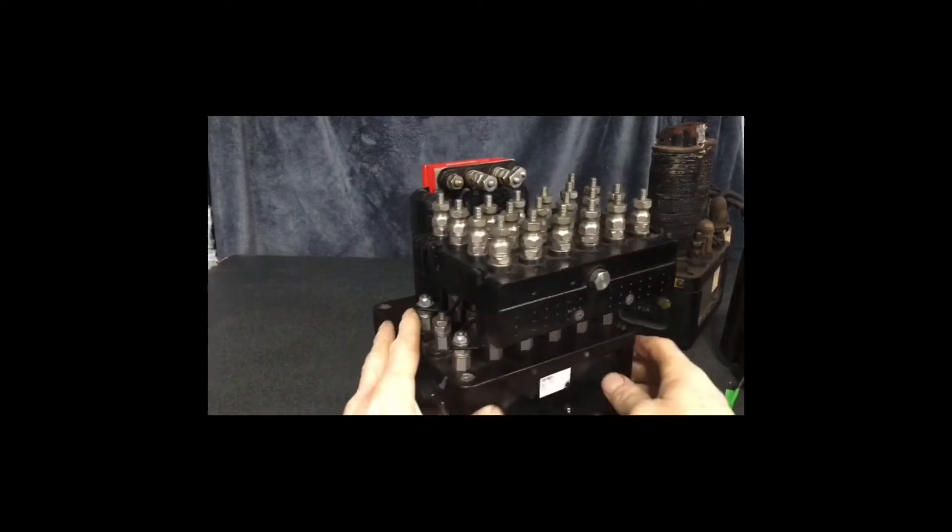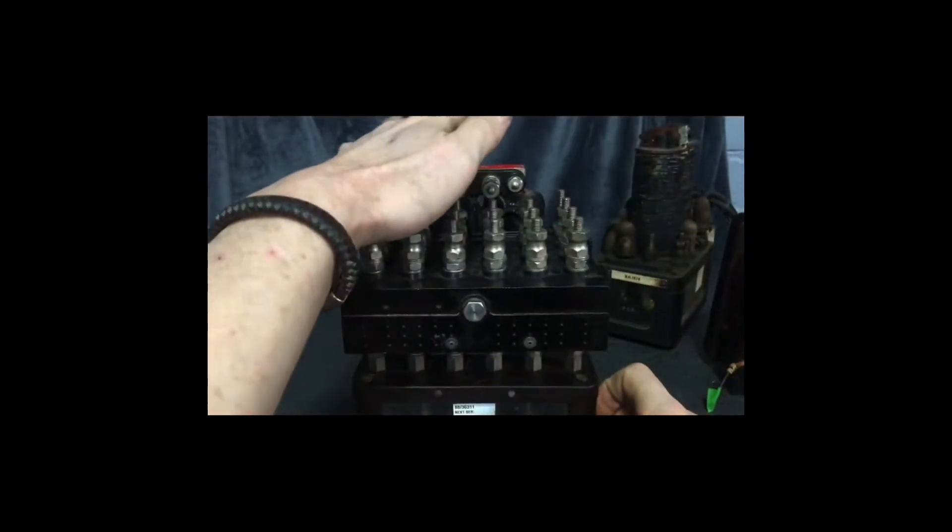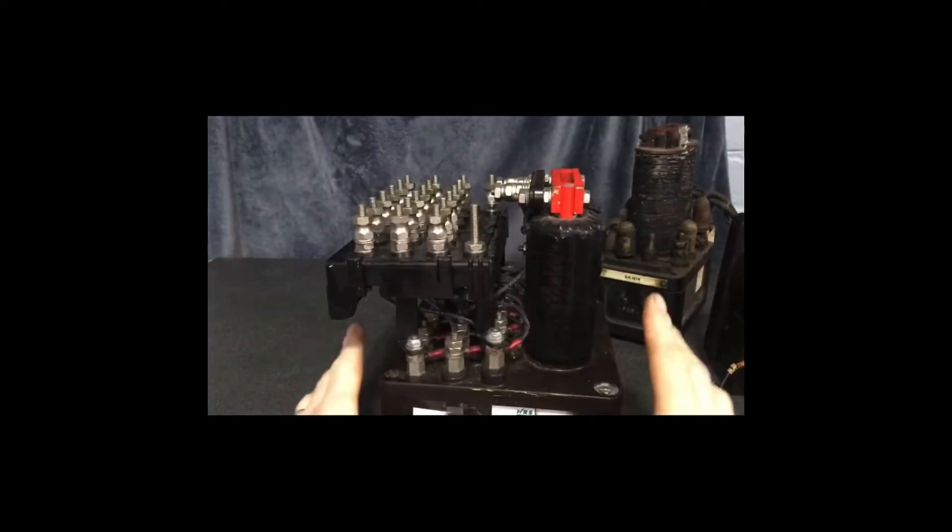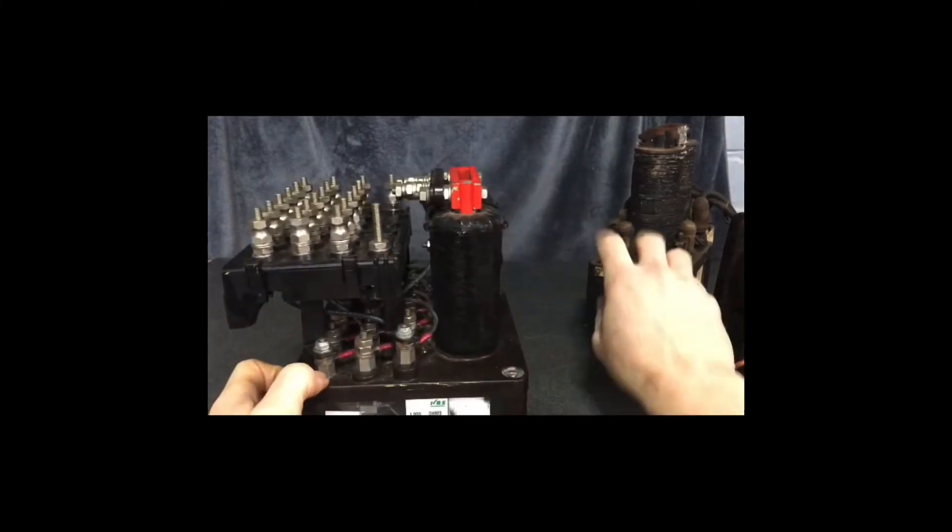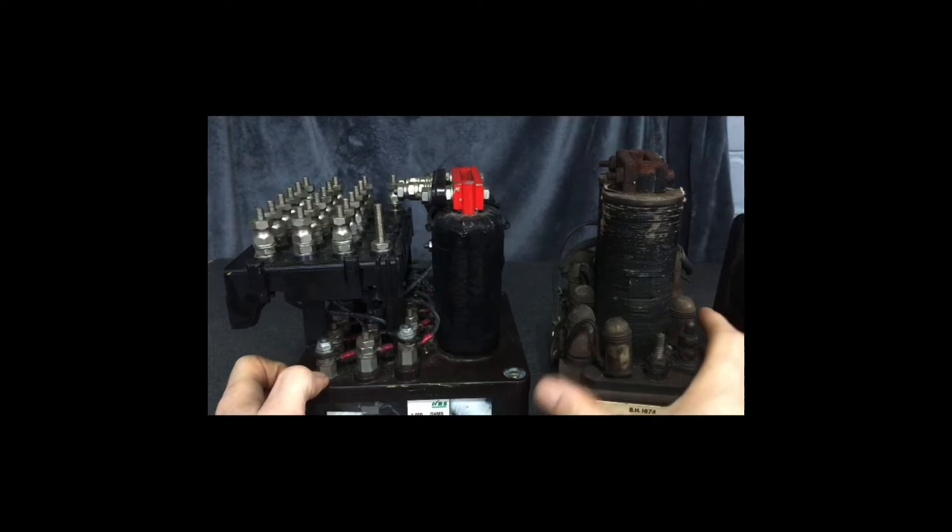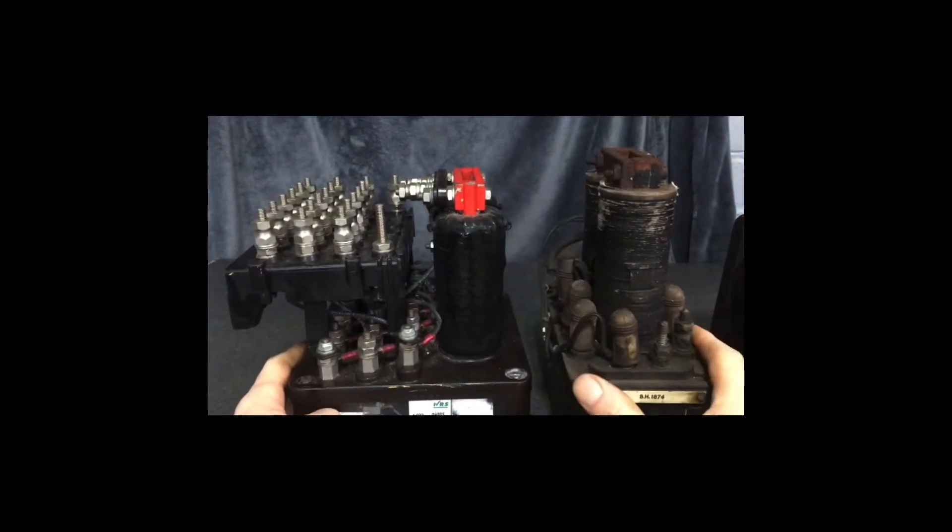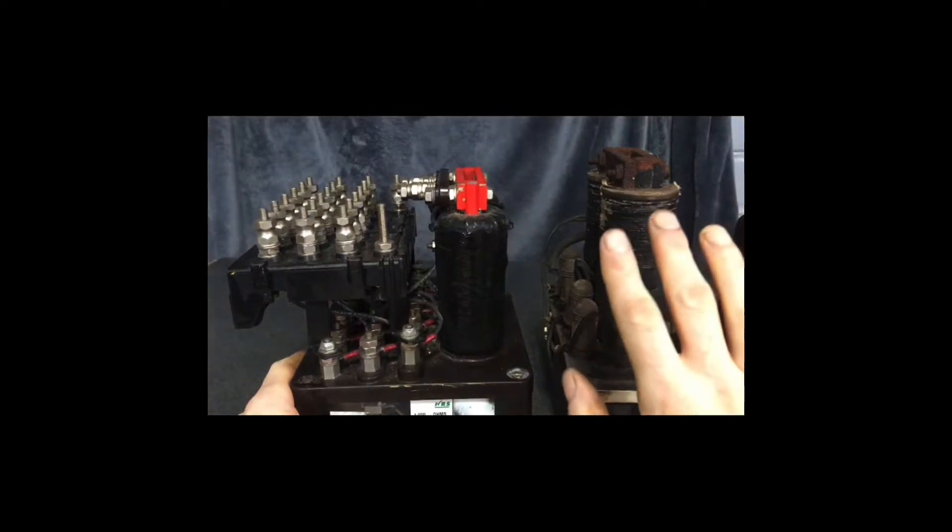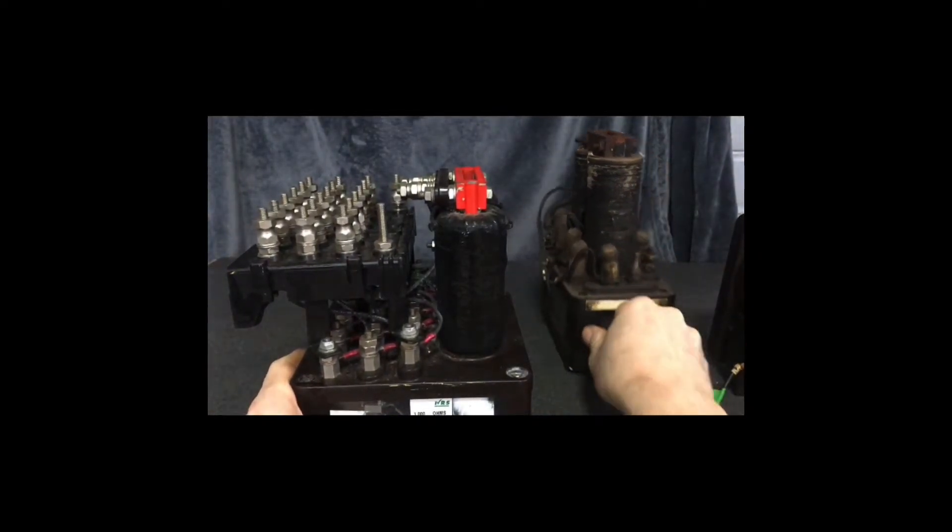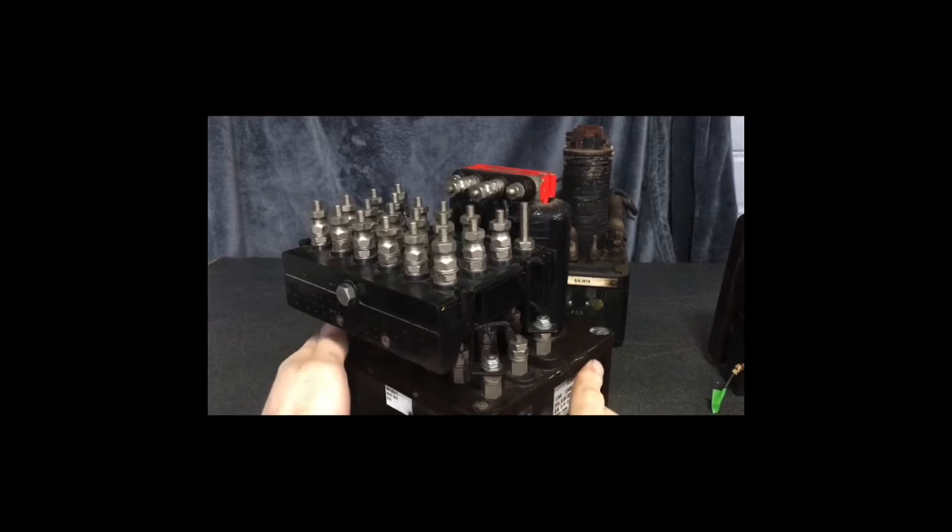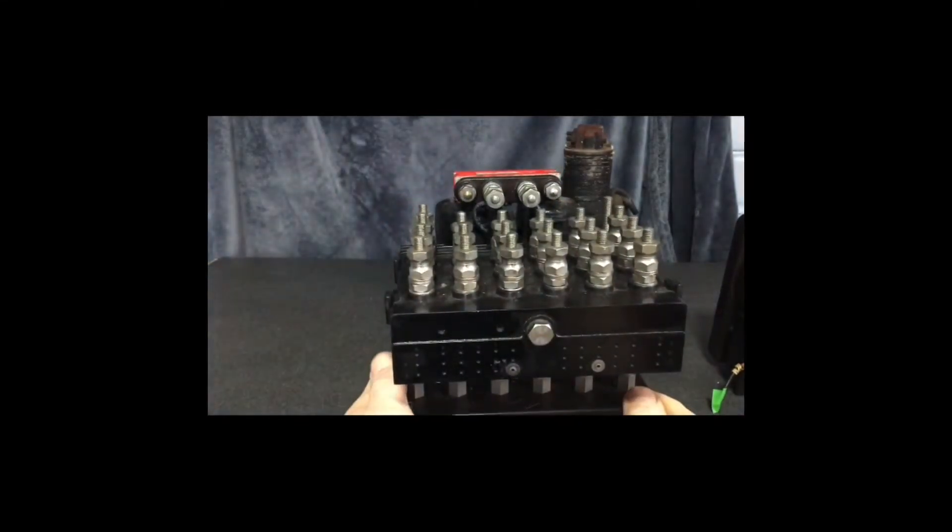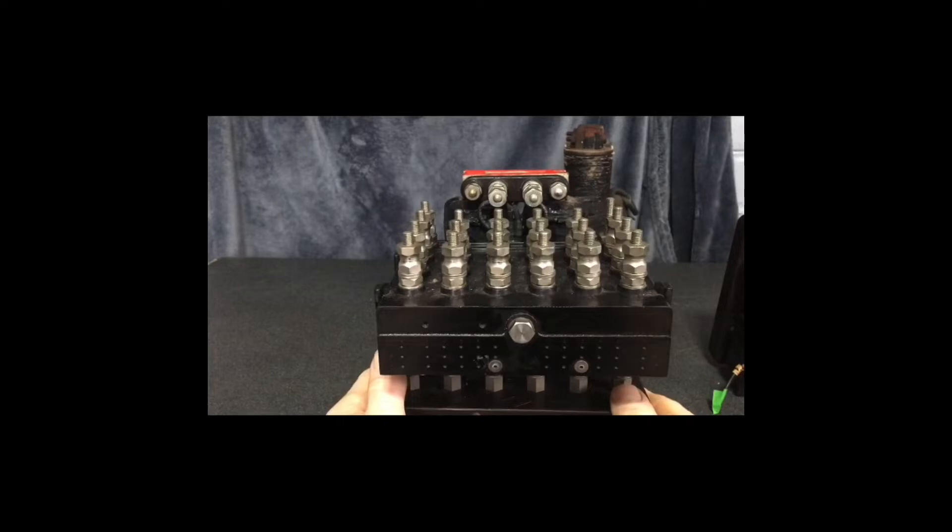You'll notice this one has a red band across the top there. Now that's quite important. This one doesn't. Track relays and other relays such as this lamp proving relay, they're all designed to work at different voltages. However these are all low voltages, low currents. This relay is a line relay. That red band means that it can be used off say 12 volt interlocking.